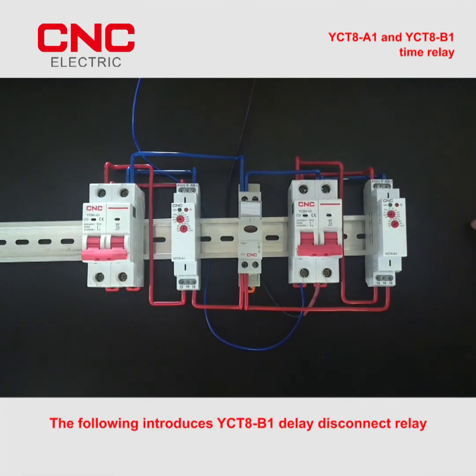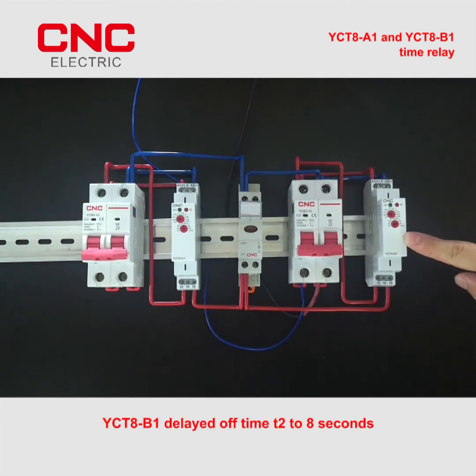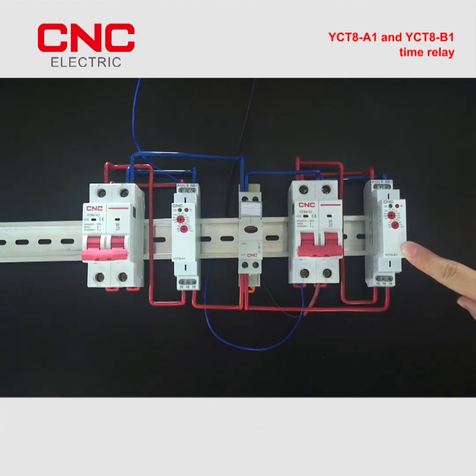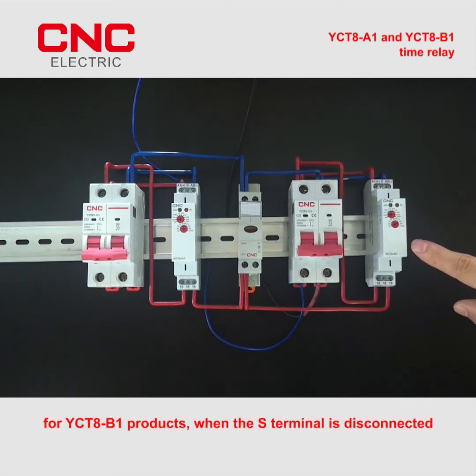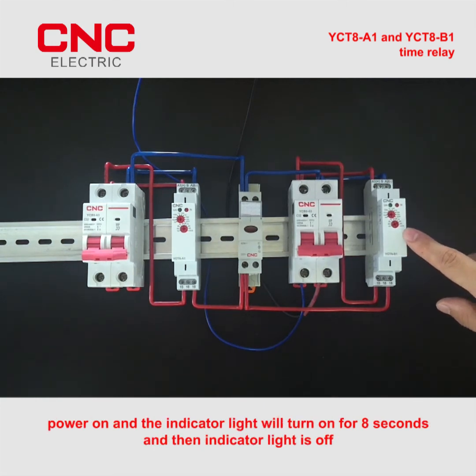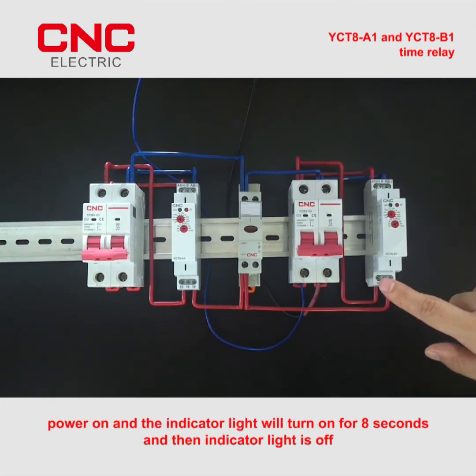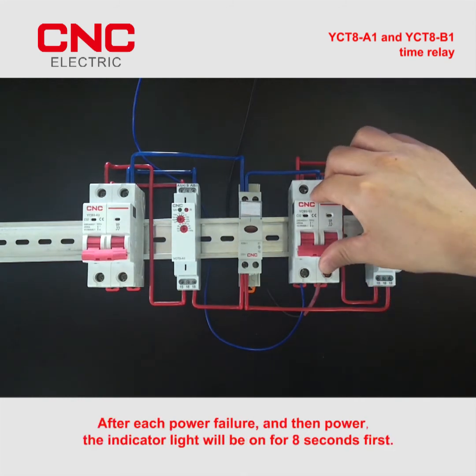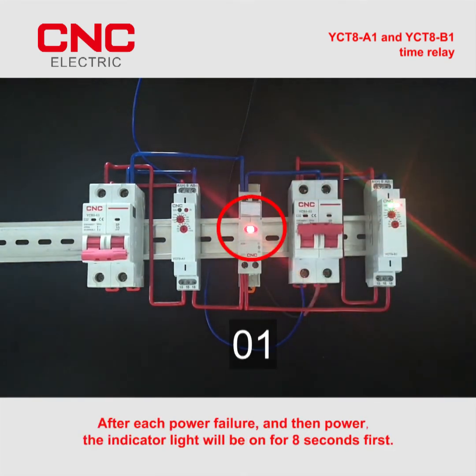The following introduces YCT8B1 delay disconnect relay. YCT8B1 delayed off time T2 to 8 seconds. For YCT8B1 products, when the S terminal is disconnected, power on and the indicator light will turn on for 8 seconds and then the indicator light is off. After each power failure, and then power, the indicator light will be on for 8 seconds first.